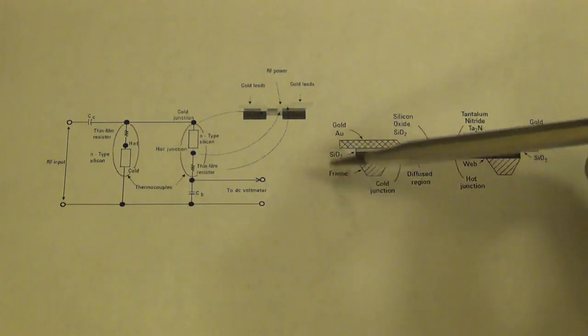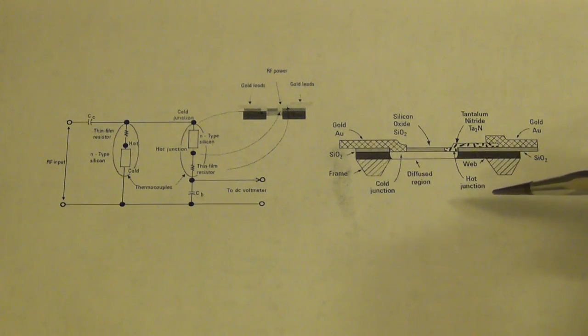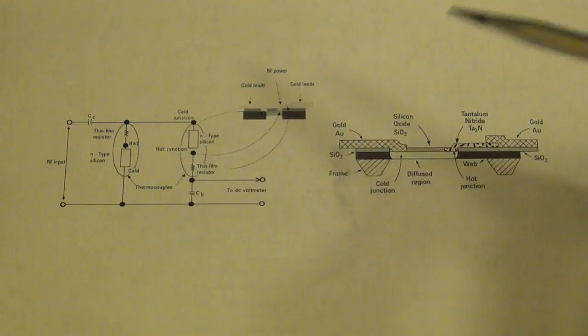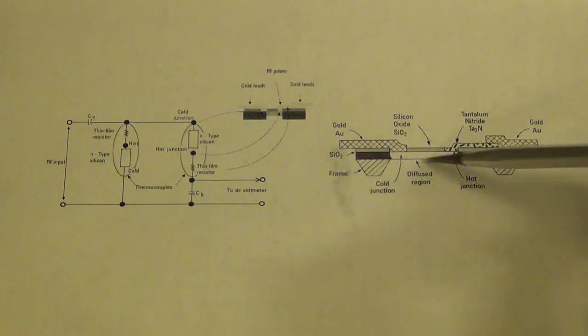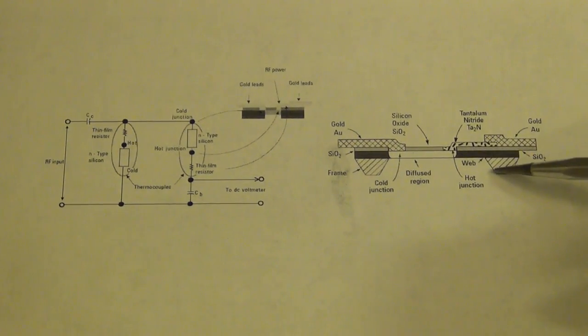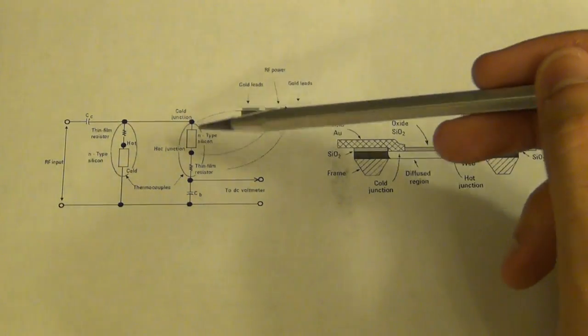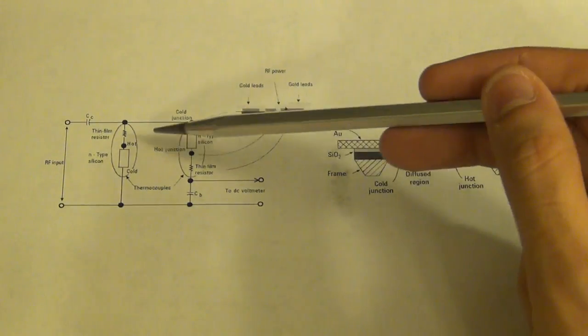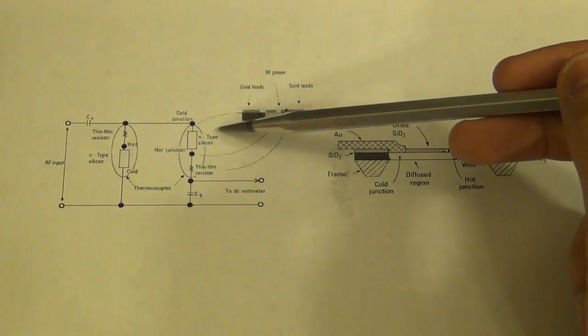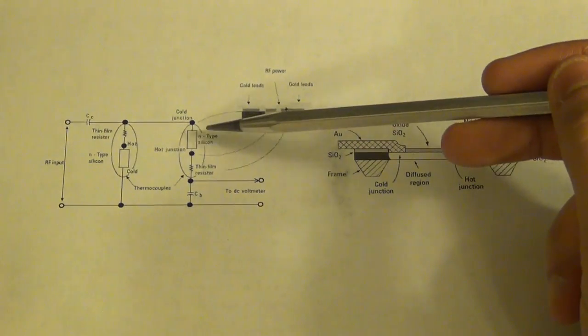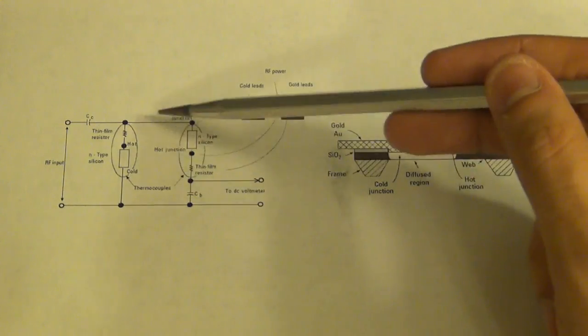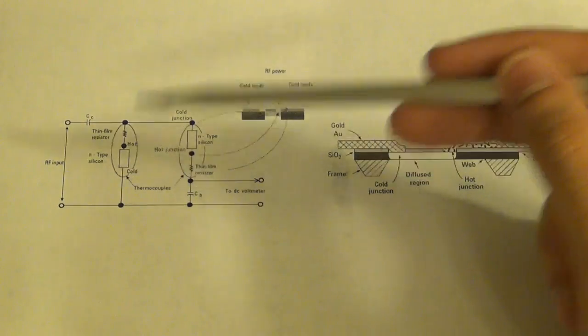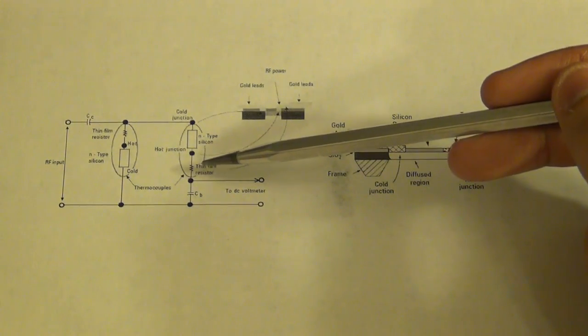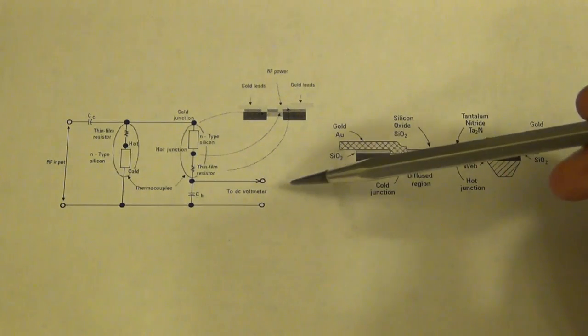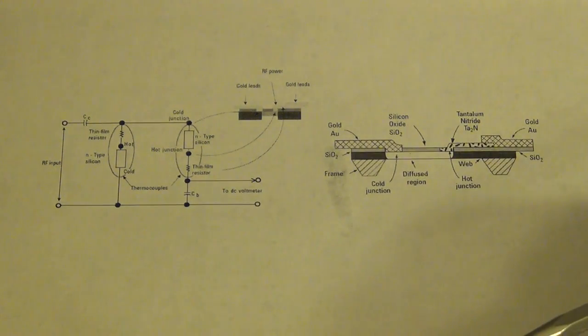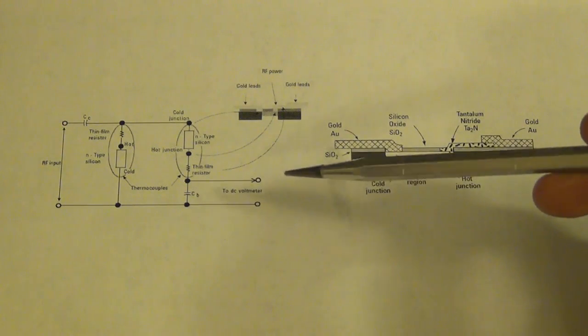So the temperature gradient developed in this type of semiconductor is going to be proportional to the RF power, and with a proper calibration curve, you can take this semiconductor piece and connect it on 2 different points where you can have a hot and a cold junction, and then you can have an N-type silicon on one side, and then switch it to the other way, so you can have a reference measurement point and one point that's actually exposed to the RF, and take the difference and go to a multimeter and then measure essentially the power that's coming in.